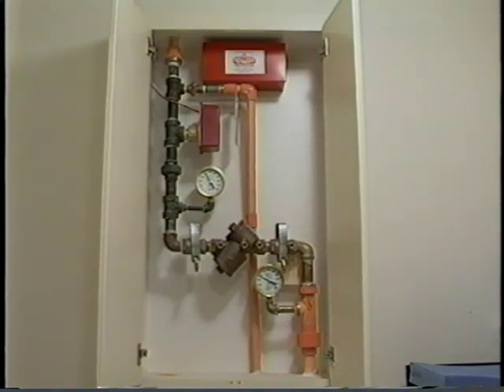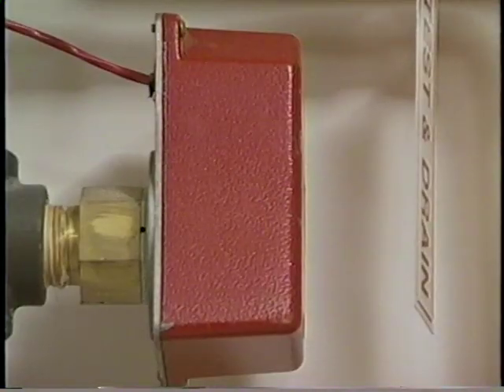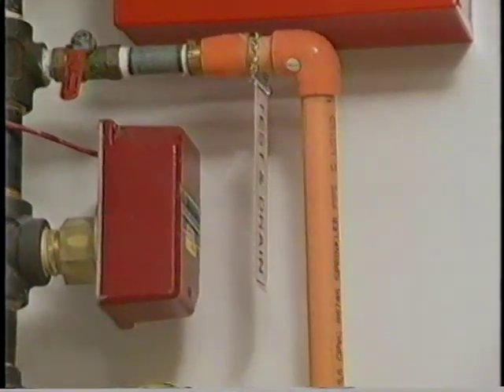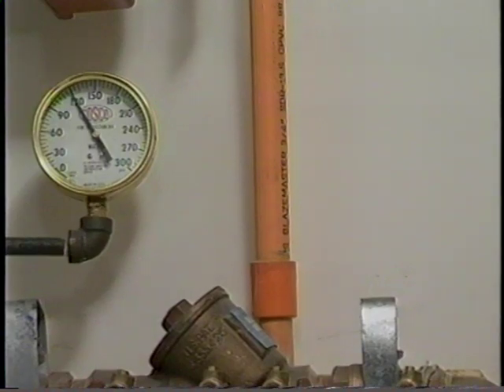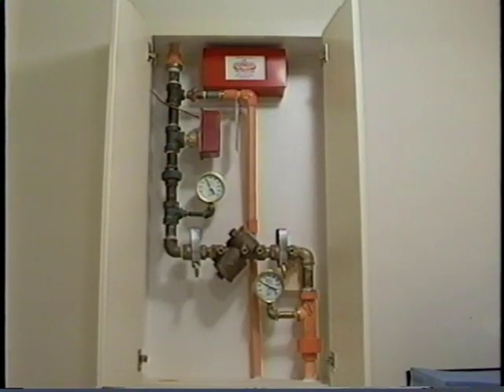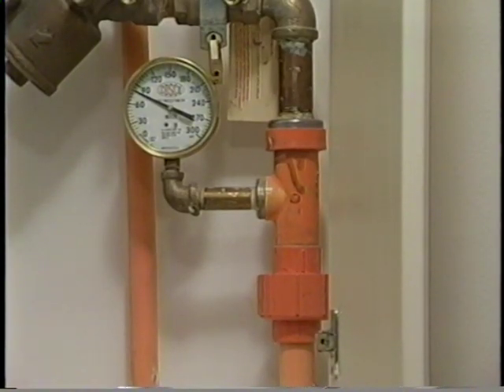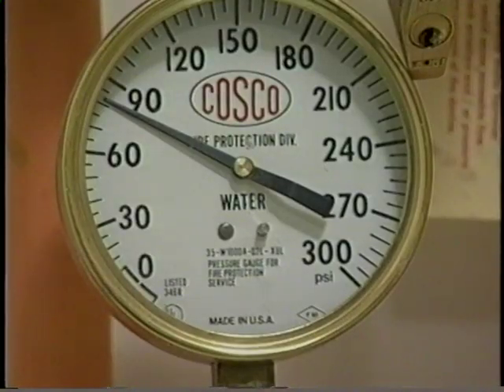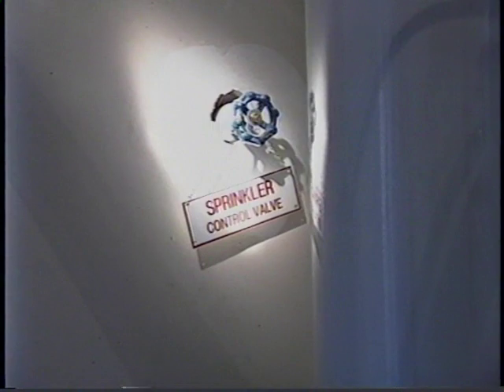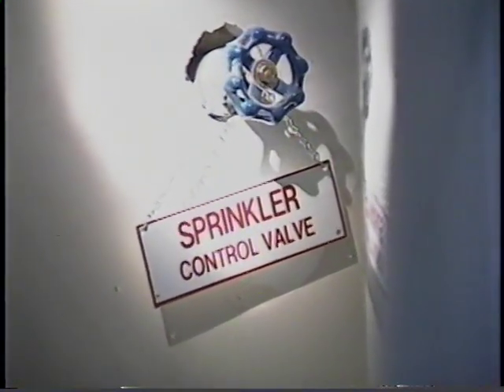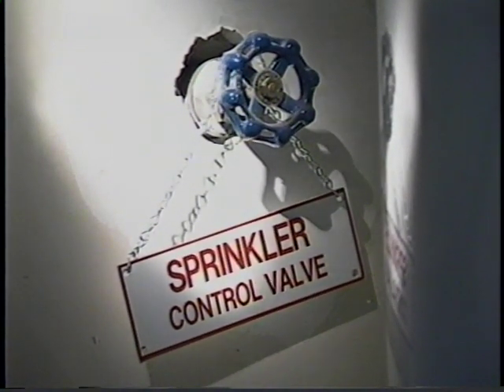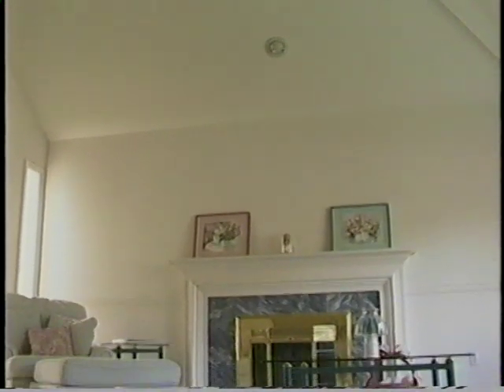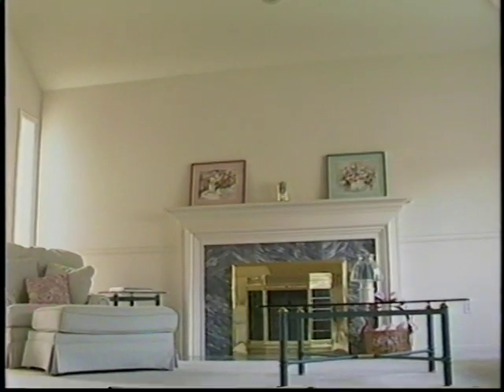Residential sprinkler systems must have a pressure gauge, flow detector, and draining and testing capabilities. They can either be connected directly to the city water supply or be tied into the home's domestic water system. A control valve is needed in either case to allow the water supply to be shut off. Residential sprinkler systems operate the same way as other wet or dry systems.